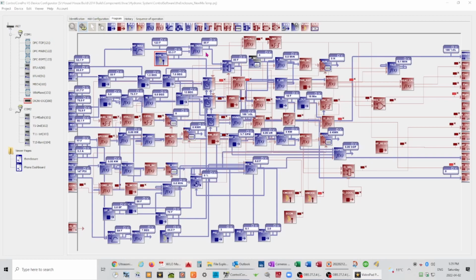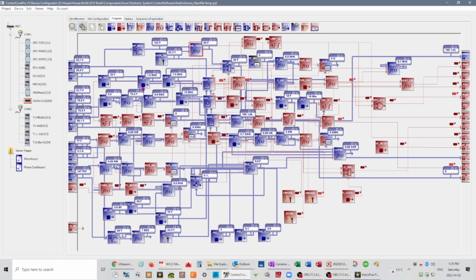52.1 degrees Fahrenheit. I have allowed for the buffer tank temperature, which is the hot water target temperature, to be 2 degrees higher than our ceiling panel supply temperature. And I've set the on dB to 1.5 degrees and the off dB to 7 degrees. So this means that our buffer tank temperature will never drop below our target panel supply water temperature. And in fact, it will always be 1/2 degree above the target panel supply temperature. This means that the buffer tank will cycle between 1/2 degree above our ceiling panel target temperature and 7 degrees above our target temperature.